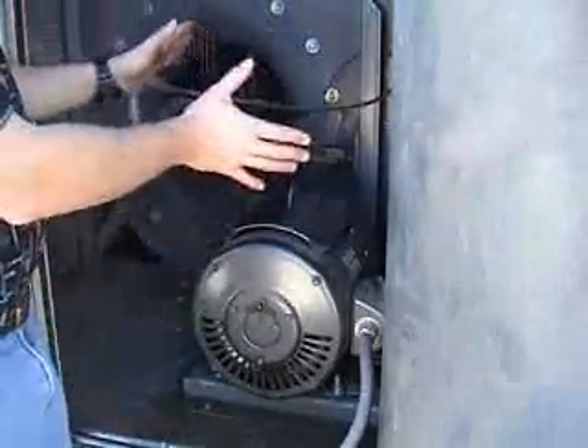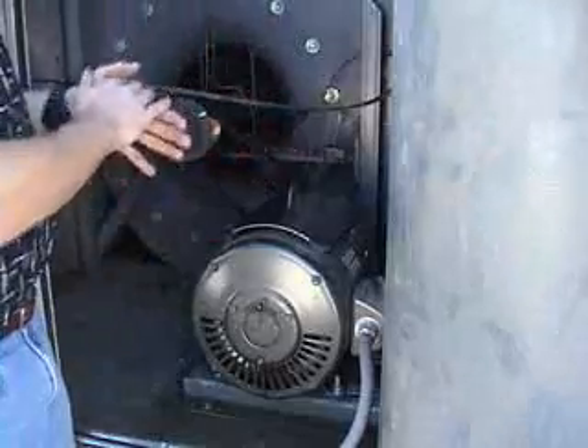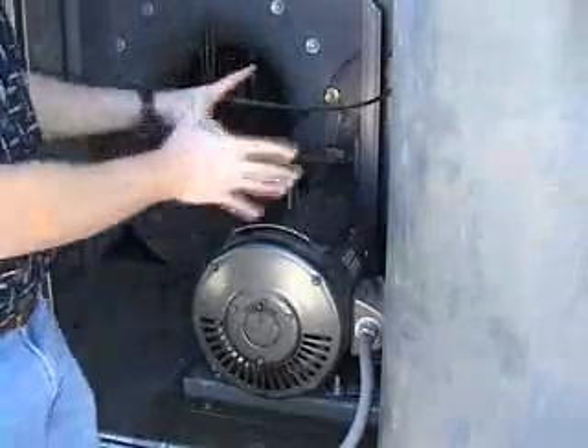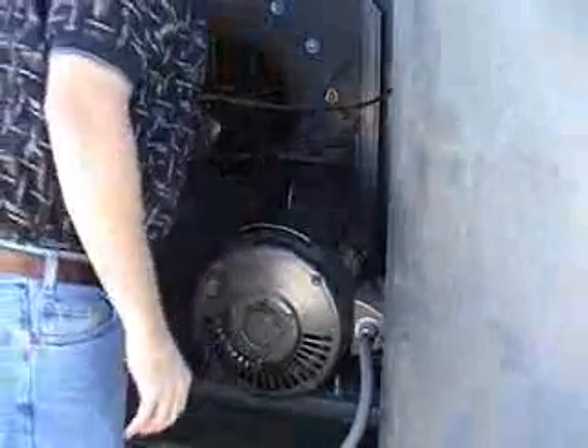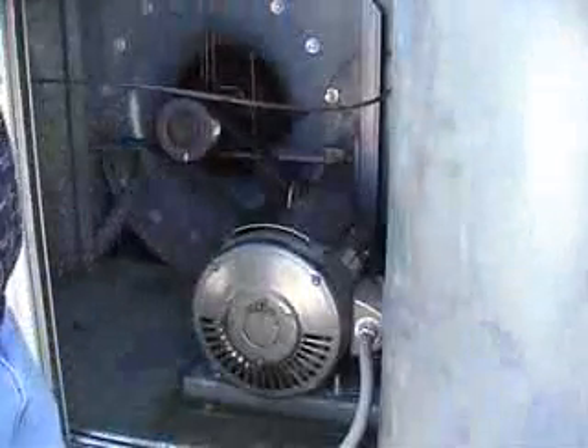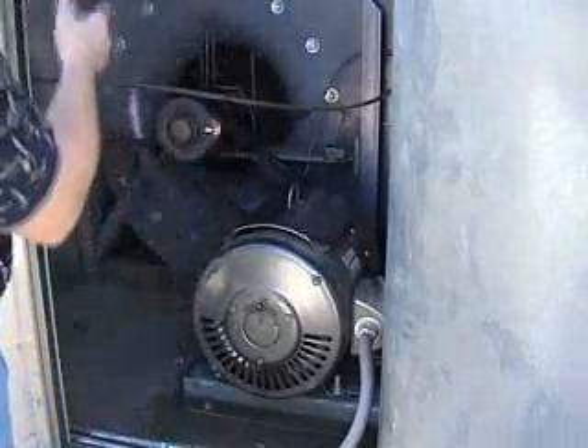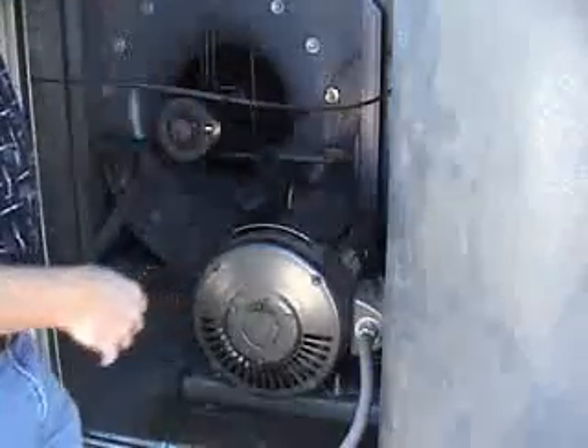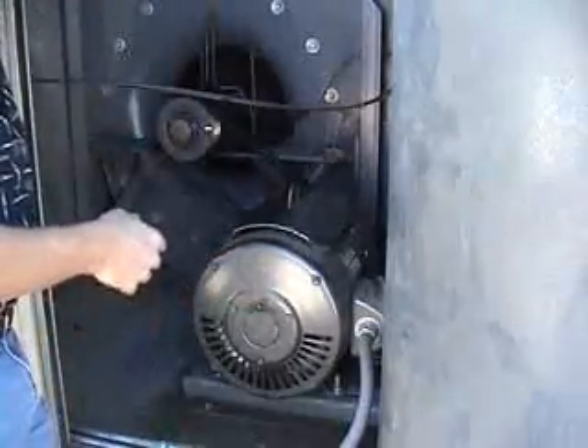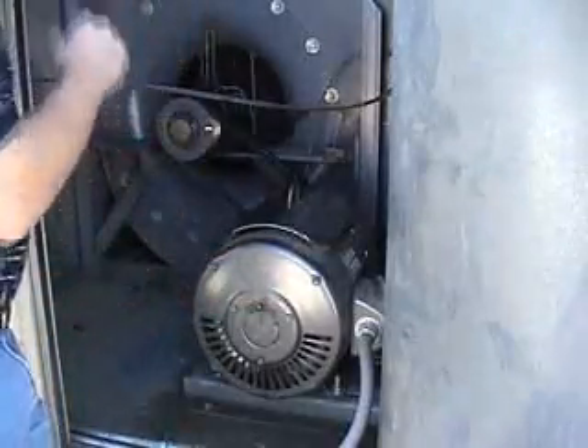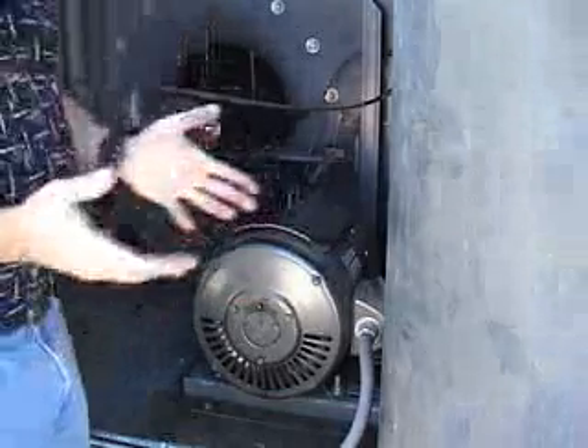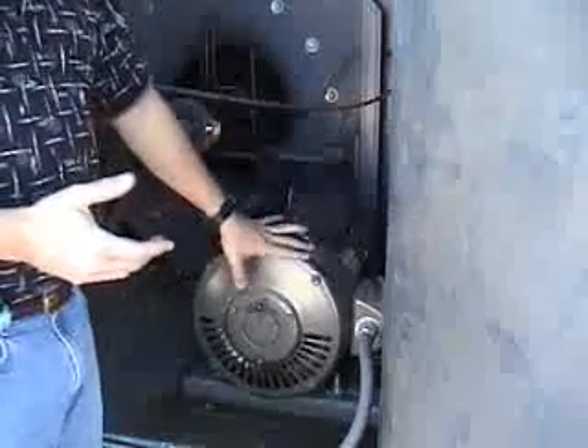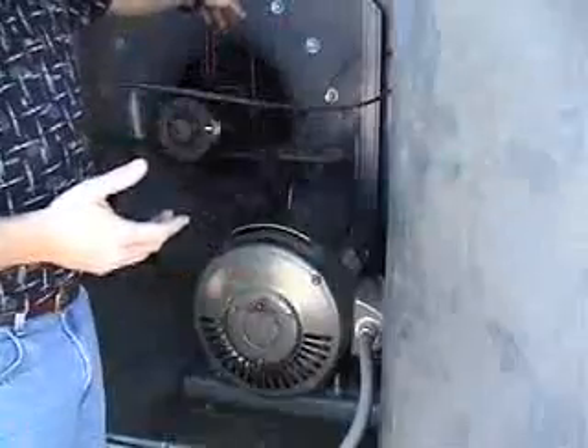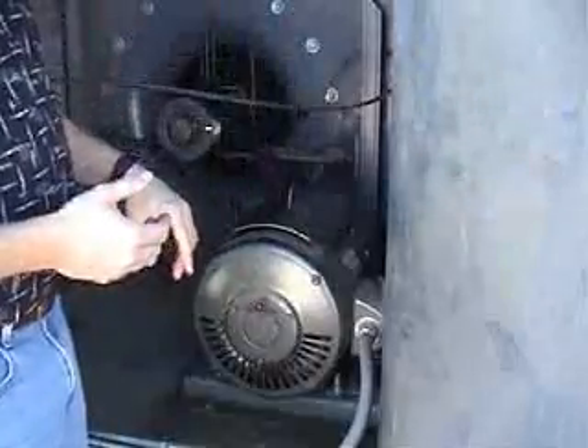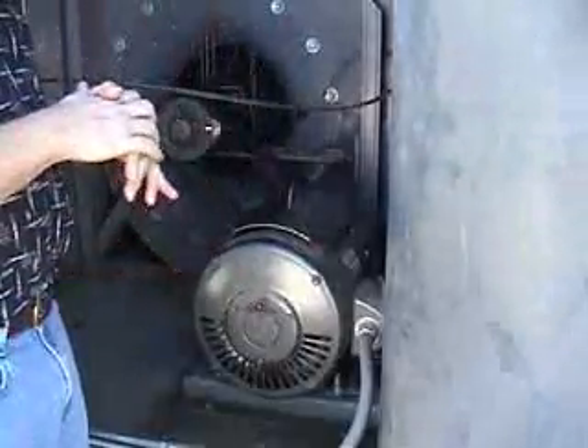Inside of this housing is a negative pressure, which would probably be about an inch or so of negative pressure inside of here. You see this turns the fan wheel counterclockwise here, and we blow the air into the other part, which is the supply pressure, and we might develop upwards of 5 inches of static on the supply side of this fan. But we use that variable frequency drive to control how fast this motor is turning, and therefore control how fast our fan is turning, which changes our static pressure.